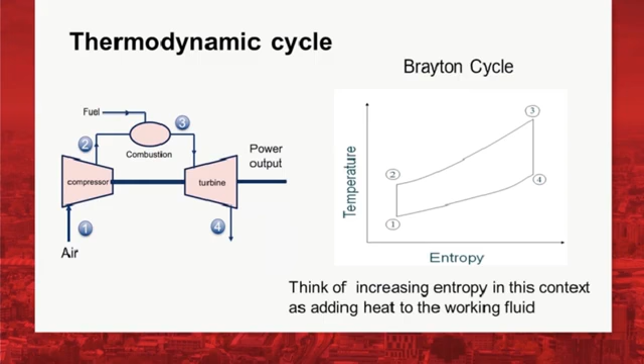Microgas turbines operate an open cycle where gases are ejected to ambient at point 4. In closed cycle systems, a heat exchanger is required to cool the working fluid, bringing the gases from the temperature at point 4 to the temperature at point 1 on the temperature-entropy diagram.